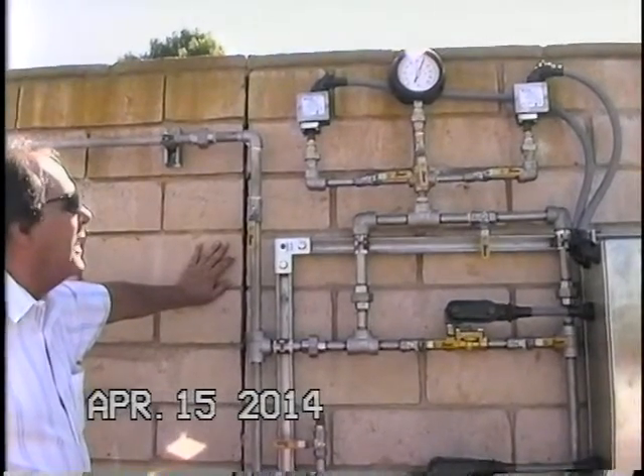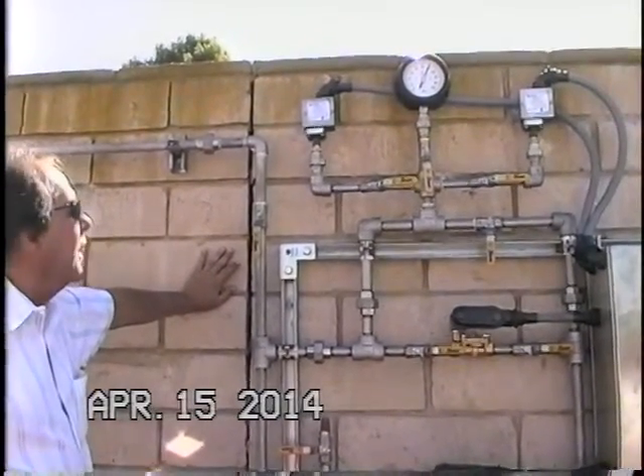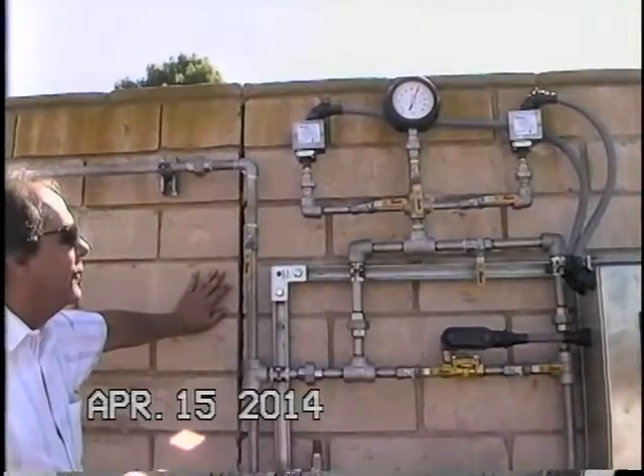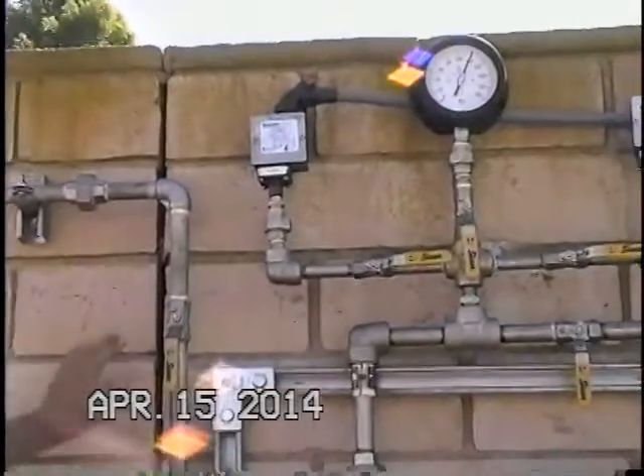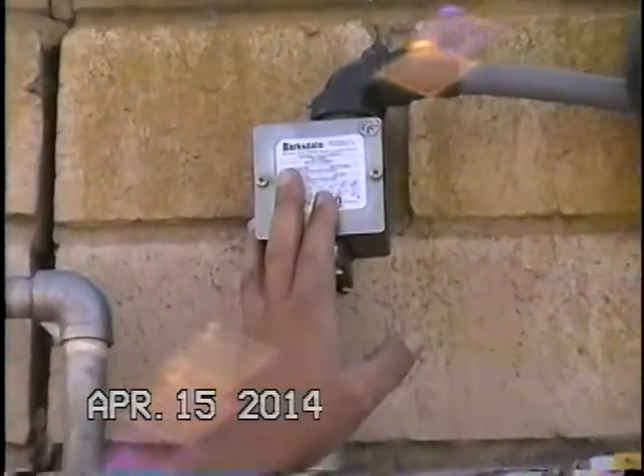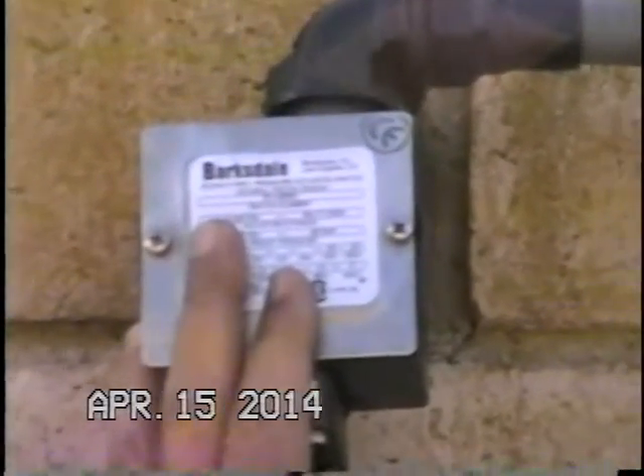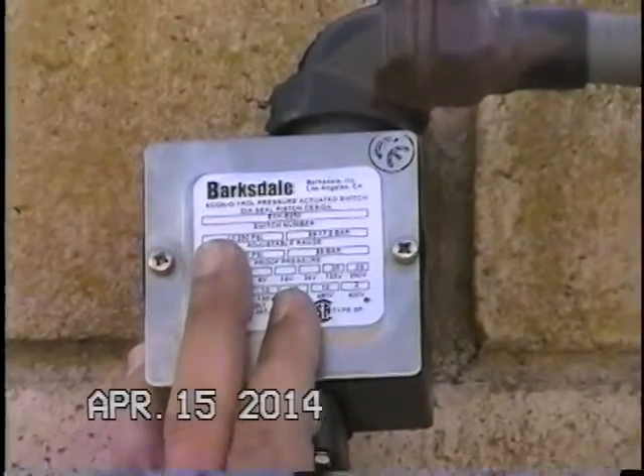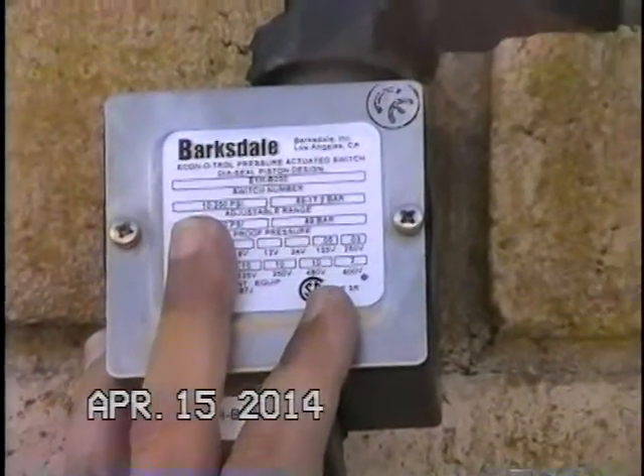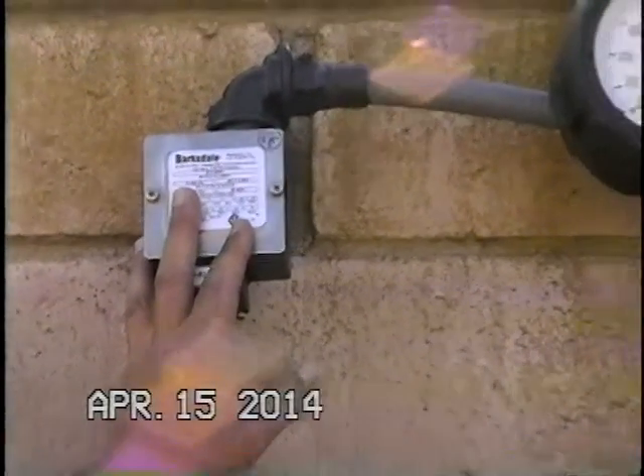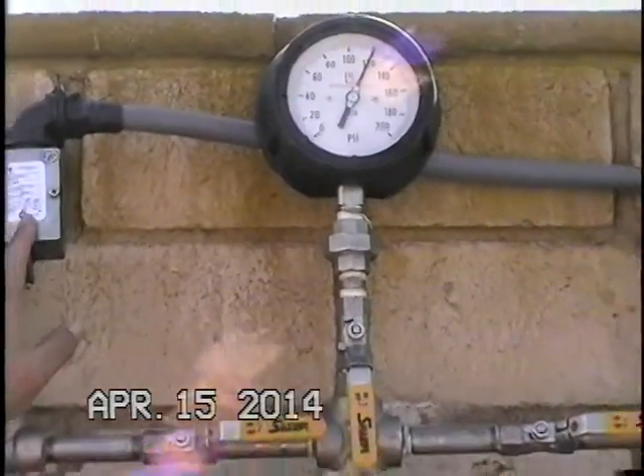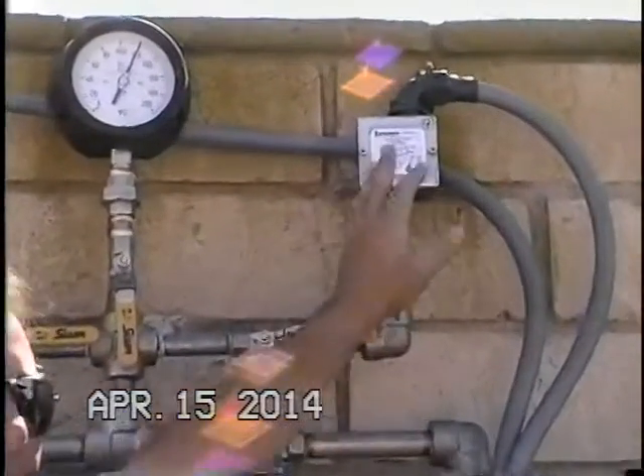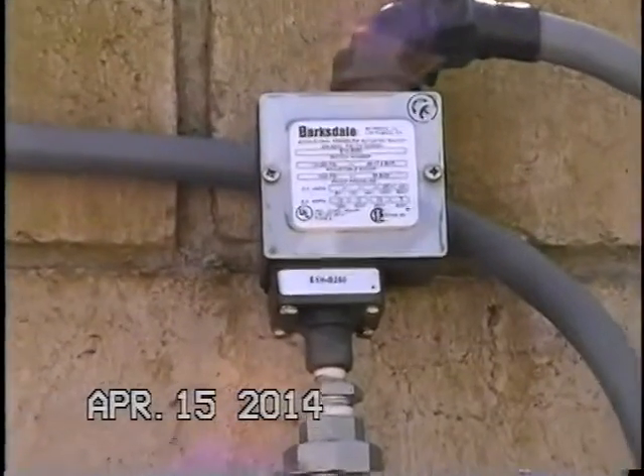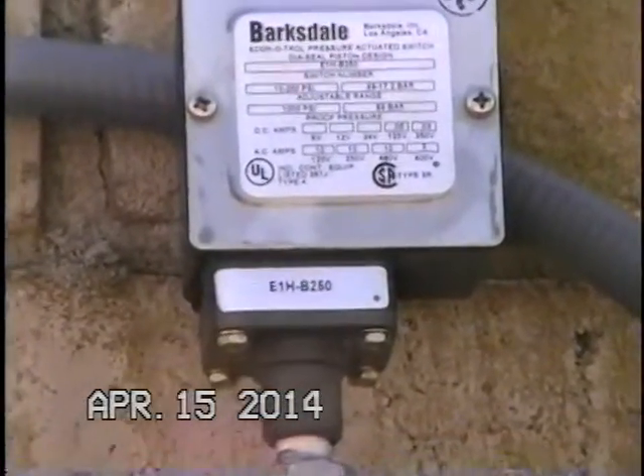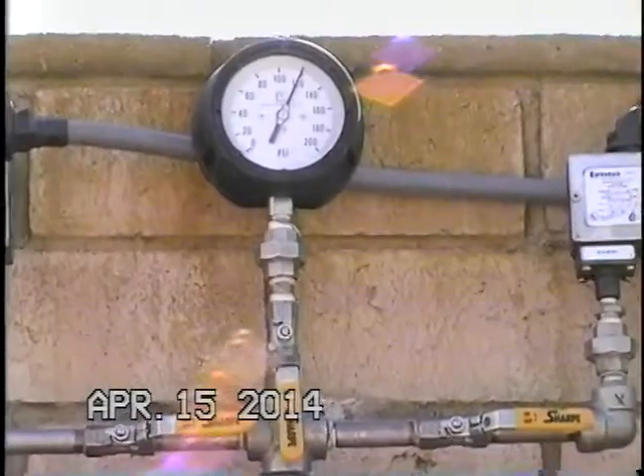They have a little added feature in here, which is a good thing. We've got a high pressure switch in case there was a high pressure condition within the surge tank. This is an actuated pressure switch that will send an alarm directly back to SCADA. Also, this is a low pressure alarm, and either of those two cases would certainly give an operator a reason to come out and see why those conditions exist.